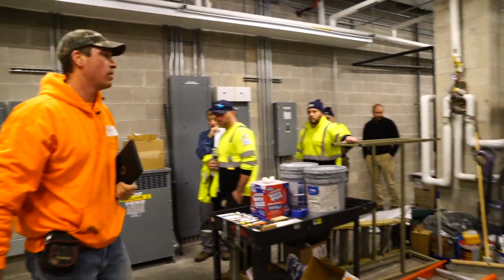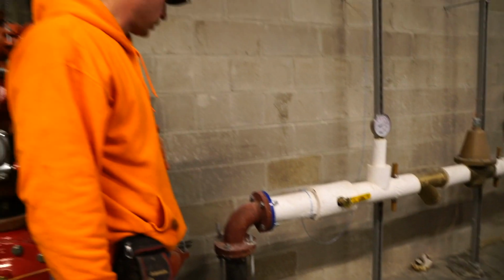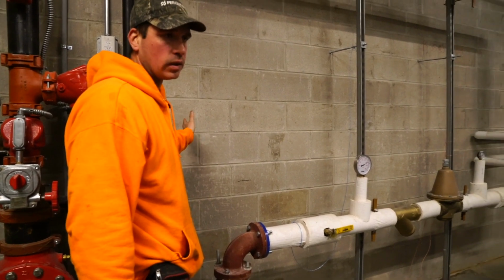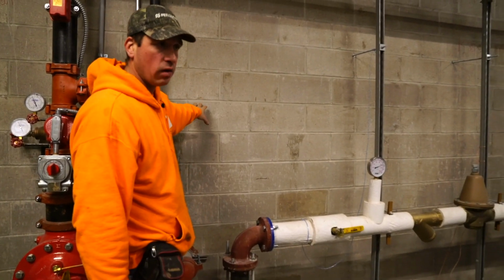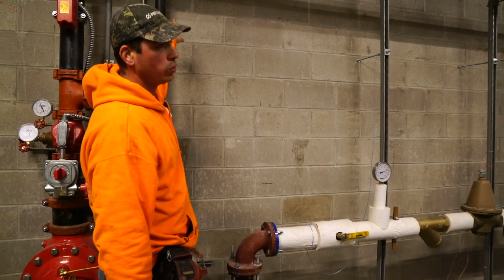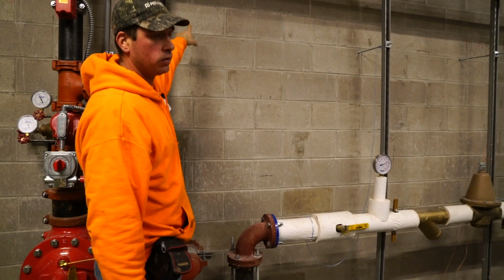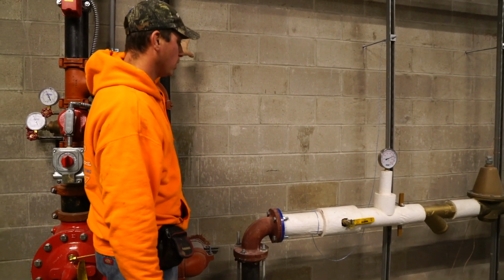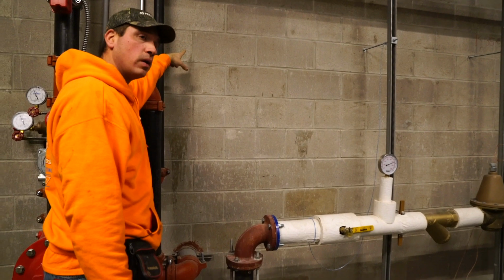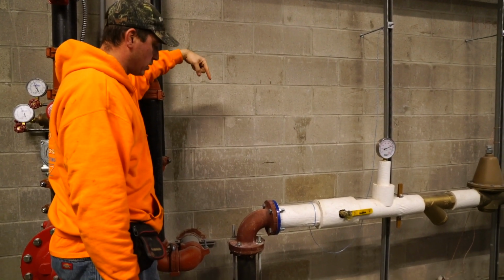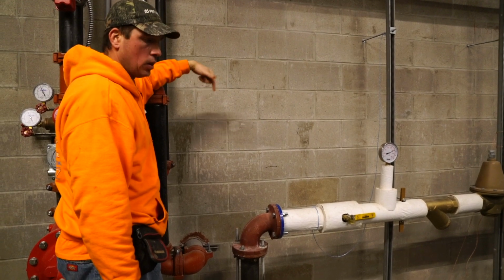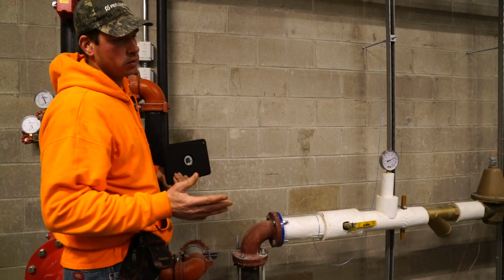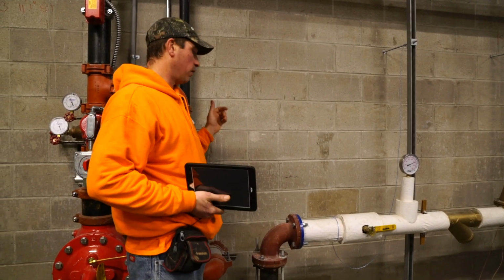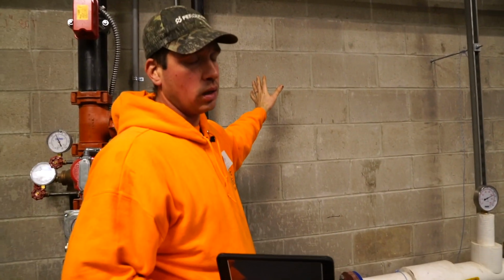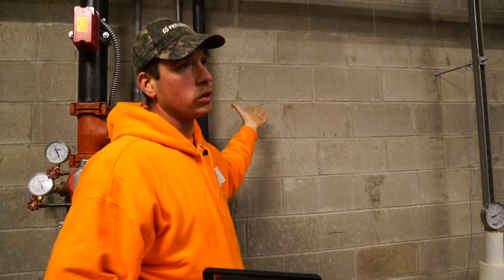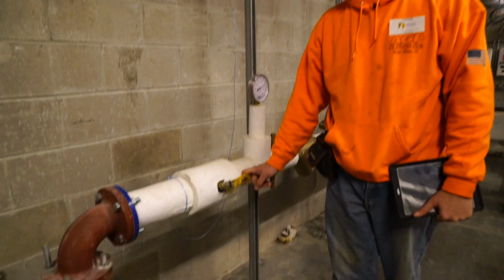I'll show you the main domestic cold water coming in. My plumbing side of my contract was 5 feet out the building, and that's it. I know right outside here you have a street valve, and this actually goes out to the pit out there. I think Vollers has to go out over that with you guys if they haven't already. There is a backflow preventer in that pit that services your domestic cold water and your fire sprinkler system. Same thing. Those backflow preventers stop any cross-contamination of anything outside of the site to come in. So those should be tested annually too. So right off the bat, you got your main valve. You can shut this off, shuts the whole building down.